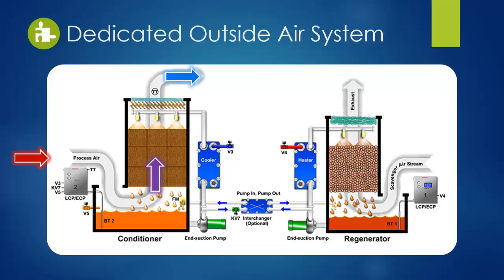In the summer, outside air will enter the conditioner. The sensible and latent heat will be removed from the air, and then the air will be supplied to the space. Next, the heat will be transferred by a heat exchanger to the return air in the regenerator. After the return air absorbs the heat, it will be exhausted. In the winter, the cycle is reversed so the supply air absorbs the heat that is transferred from the exhaust air stream.